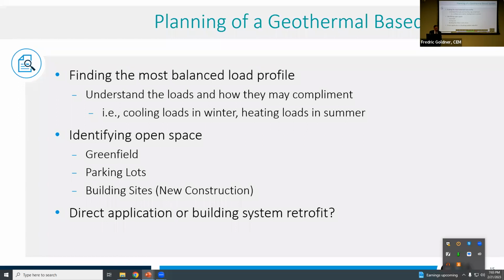One thing I want to state, in case not everyone is familiar: a heat pump simultaneously produces heating and cooling whenever it runs. There's a hot side to the geothermal heat pump as well as a cold side. So you can literally make the energy for a cooling coil, for an air handler, and the heat coming out of your geothermal heat pump, which is very hot, 90 degrees or greater, could immediately go into your building's potable hot water storage tank across a heat exchanger, of course. You could literally cool your cooling process before you have to re-enter into the ground.